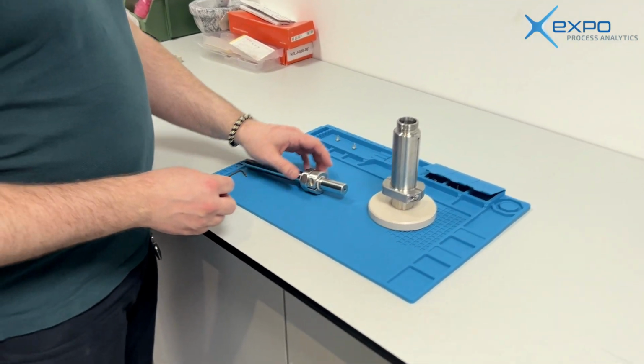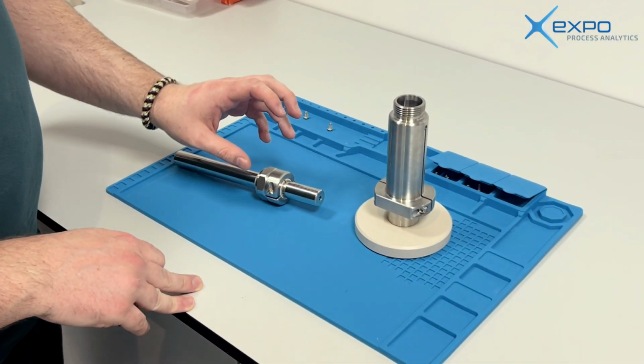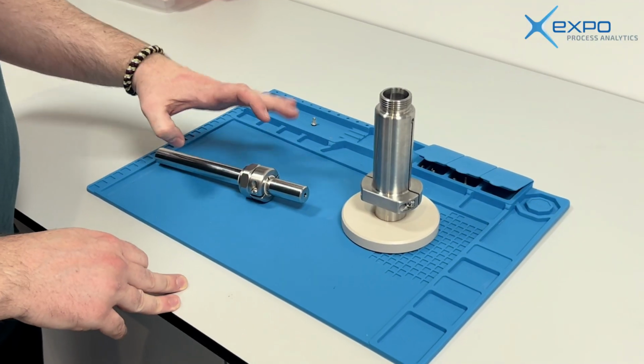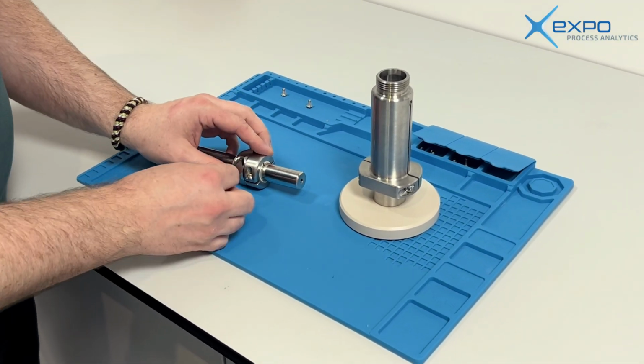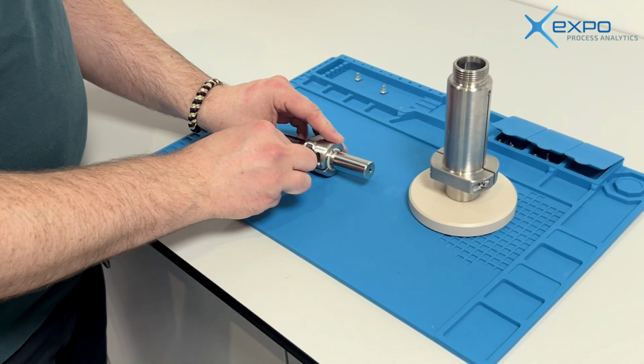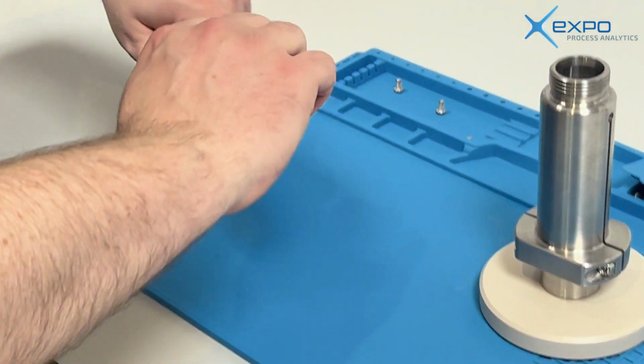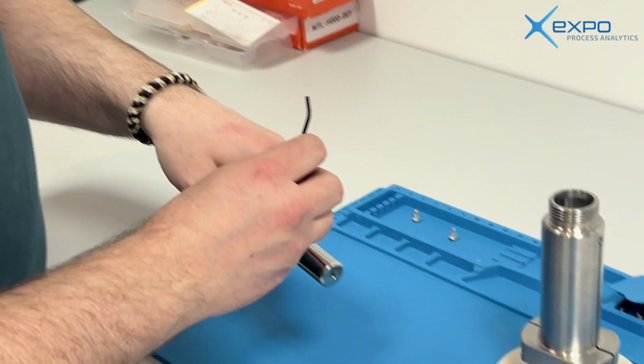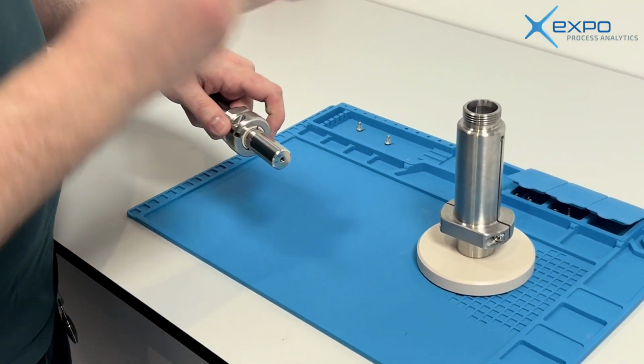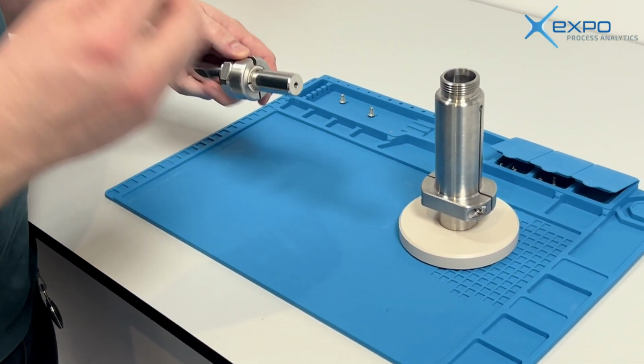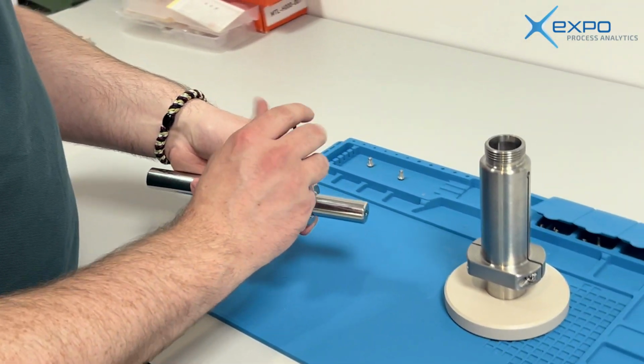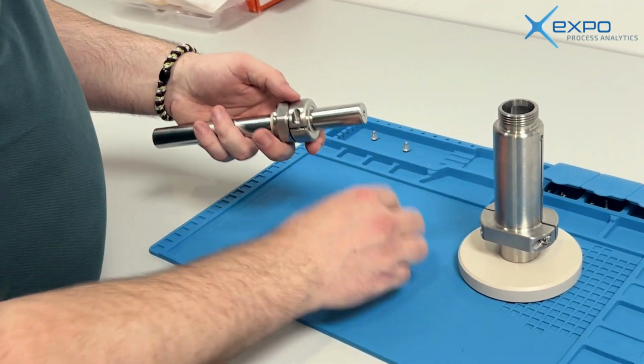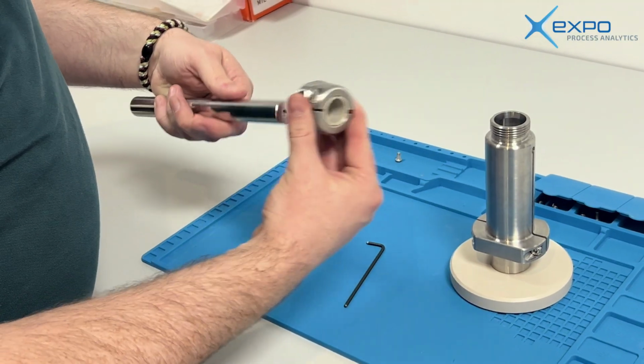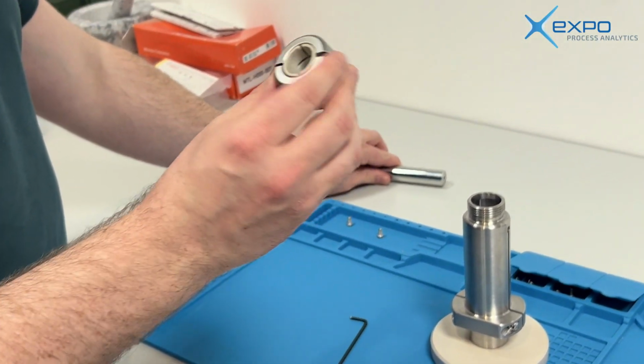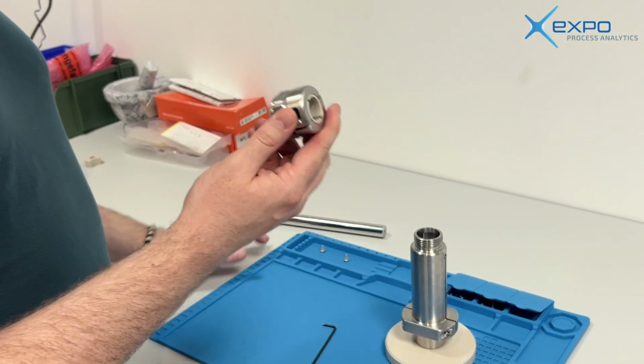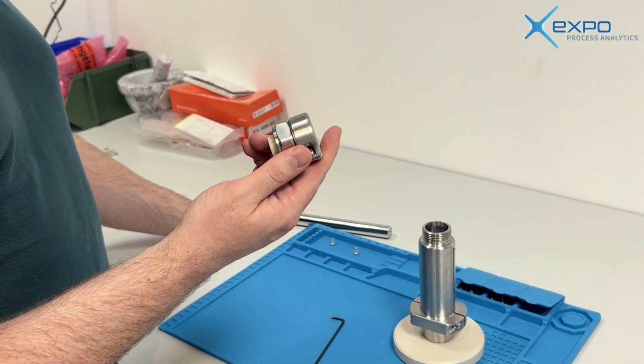Okay, so at this point what you want to do is take the compression fitting and clamps off the dummy probe and put them onto the actual probe. So all you need to do is loosen, not remove, the two fasteners on the back of the clamp. Again, this would normally be torqued to a predefined value. I'm just torquing them loosely for demonstration purposes. But you just have to loosen them a little so that it can slide off, and actually that can then become sort of one sub-assembly that you can move to the actual probe in its entirety.